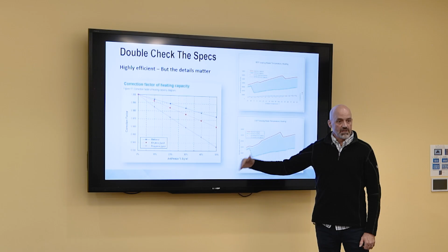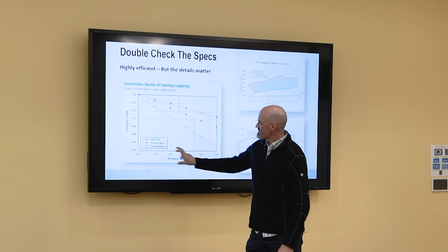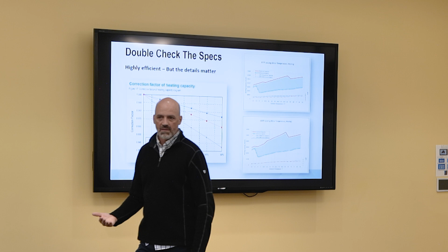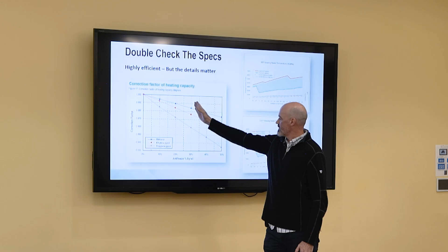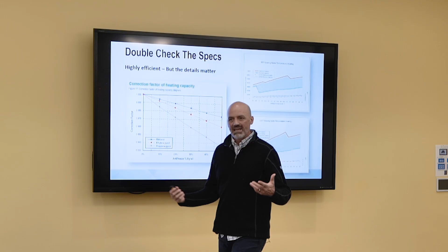This chart is about the antifreeze derate, a correction factor. The more antifreeze you have, and the colder it gets, the more antifreeze you have to put into the water, and the more antifreeze you put in, the more of a derate you have. These are different types of antifreeze, and this is the percentage of antifreeze by weight. So if you're having to put in 30% antifreeze, you're going to take a 2 or 3 or 4% derate on capacity. It's there, it's not a lot, but it's part of the details to be designed.